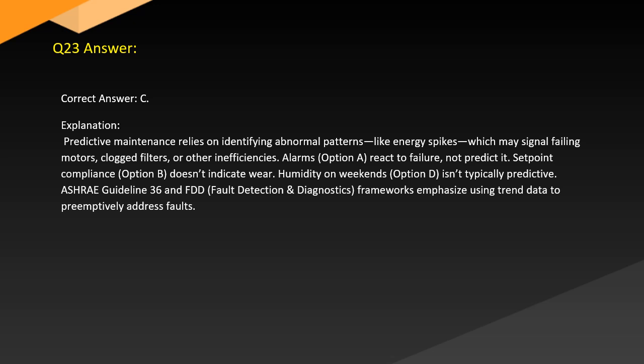Answer. Correct answer: C. Explanation. Predictive maintenance relies on identifying abnormal patterns, like energy spikes, which may signal failing motors, clogged filters, or other inefficiencies. Alarms, option A, react to failure, not predict it. Setpoint compliance, option B, doesn't indicate wear. Humidity on weekends, option D, isn't typically predictive. ASHRAE Guideline 36 and FDD, fault detection and diagnostics frameworks, emphasize using trend data to preemptively address faults.